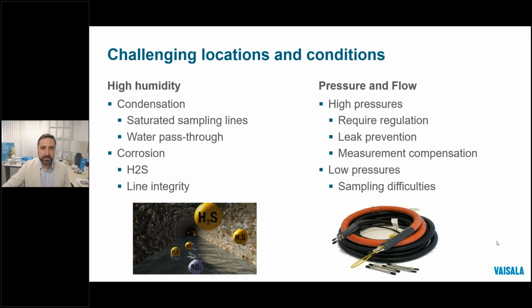And as I'm sure you're aware, measurements in biogas and RNG processes are not easy, and between the high humidity and contaminants in the system, it requires specialty hardware and sample conditioning to make sure a gas chromatograph or an extractive analyzer can measure with any reliability. This means drying the gas before measurement, which involves equipment that needs service and replacement parts. Alternatively, some sample lines will need heat tracing to limit condensation and clogging or freezing. This requires additional components and electricity while being susceptible to leaks or the occasional valve that's open when it's not supposed to be.